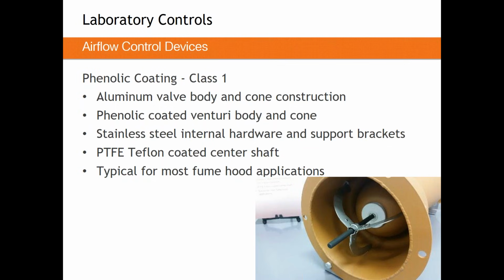In the most commonly used coated valve, we call it a class 1 valve, there are still, however, some stainless steel components. So you can see some of the mounting assemblies are still stainless steel, and some of the hardware is still stainless inside of that valve. Phenolic and stainless cover very similar spectrums of chemicals that they're resistant to. I would say 95% of fume hood valves we ship out are coated in this class 1 coating.